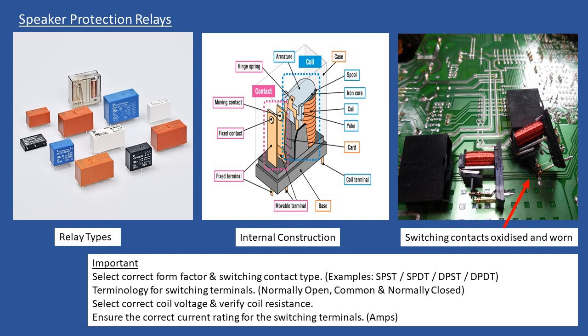When I refer to electromechanical, you can see in the video a breakdown or exploded view of what a relay looks like. You have a coil, normally with an iron core, and there is an armature at the top. When we apply voltage and current flows through the coil, the iron core creates a magnetic field, magnetizes, and pulls down the armature. Then you will see a movement. This is a mechanical movement as the armature pulls down, and normally there's a spring mechanism which will return it back to its original state when power is disconnected, and the internal contacts then change over.